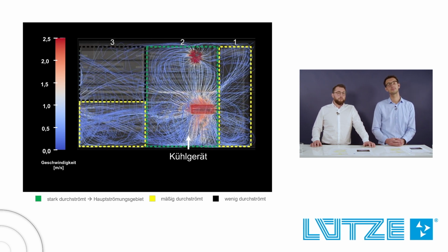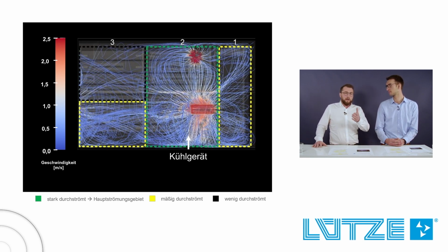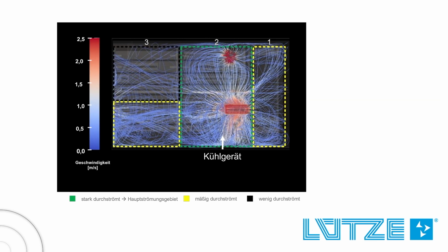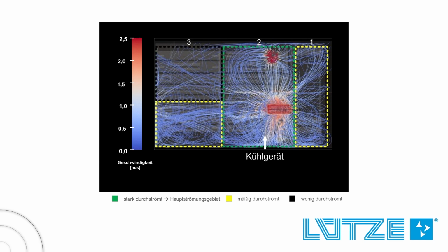Okay, understood. So by using an air blower, we could easily thermally optimize cabinets 1 and 3. That would open up the airflow layers, and with limited cooling energy, we could achieve a good climate in all 3 cabinets. Exactly. Additionally, it should be noted that each cabinet or cabinet combination needs to be considered individually. In the worst case, you still have the option to activate the cooling device for cabinet number 2 as a backup. However, the ideal scenario is to run this cooling device as infrequently as possible, only when it's truly needed, such as during hot summer months.